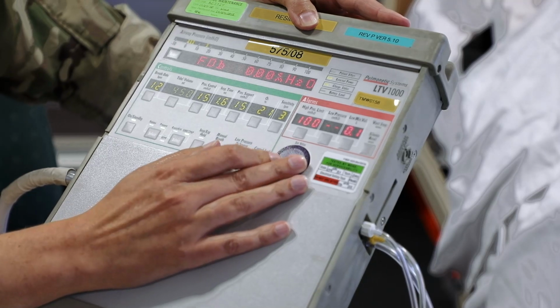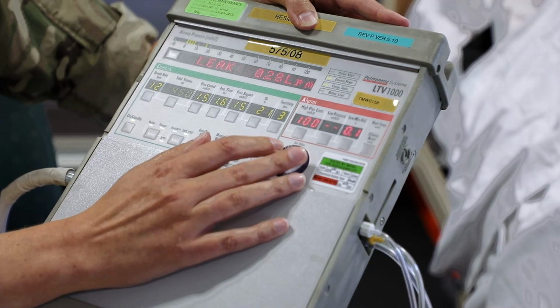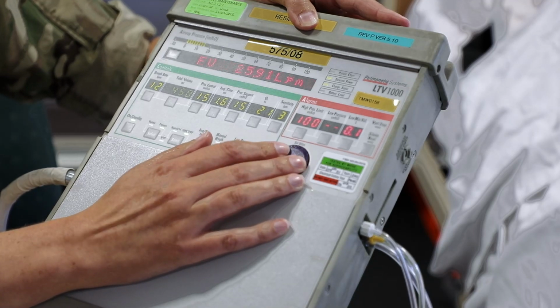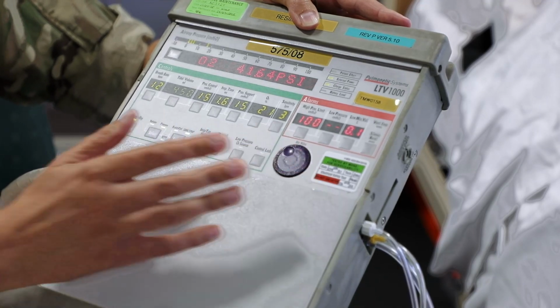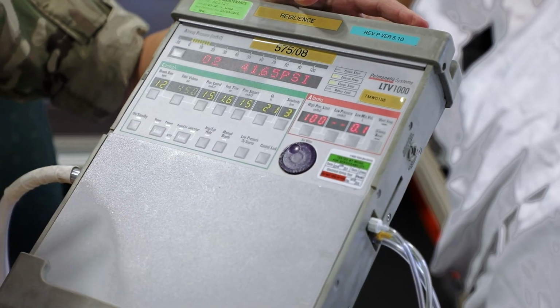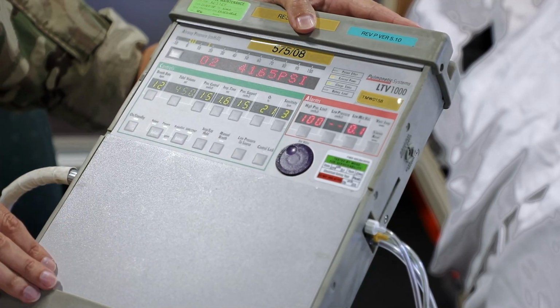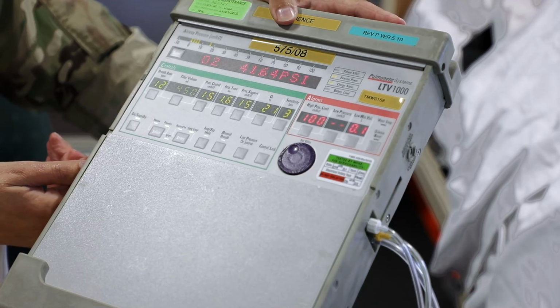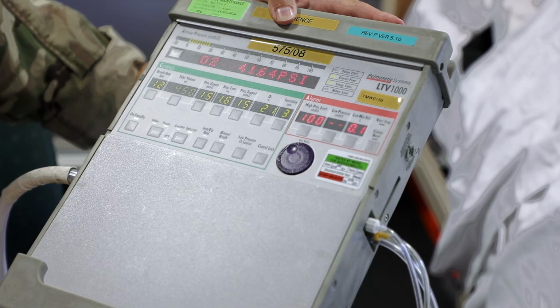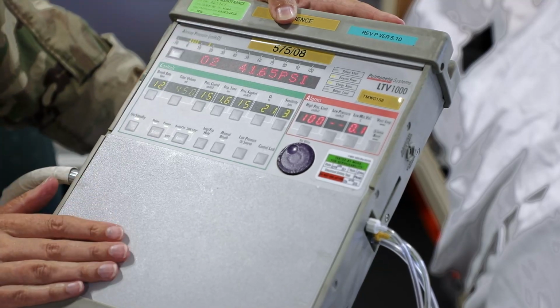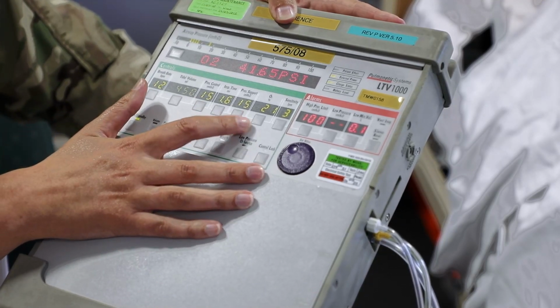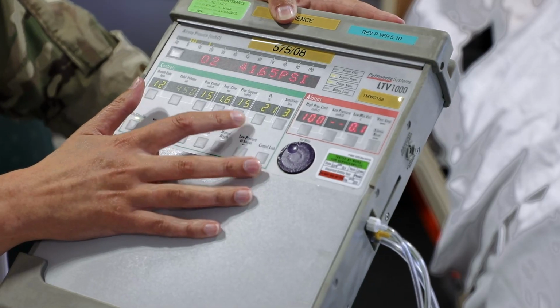A lot of these numbers we're not going to worry about, so we're just going to scroll through until we get to the first one that we worry about, which is our oxygen PSI. This should be monitoring a PSI between 40 and 80. But as we mentioned before, the actual valve set on the oxygen tubing is set at 55 PSI, so you would assume that your oxygen PSI should be about 55. Now, I'm not actually delivering any oxygen through the LTV, so we've already got a low PSI with no oxygen delivery.